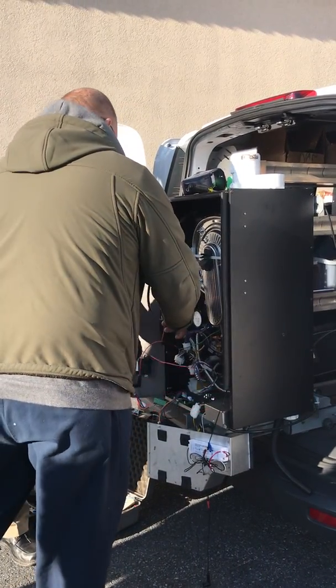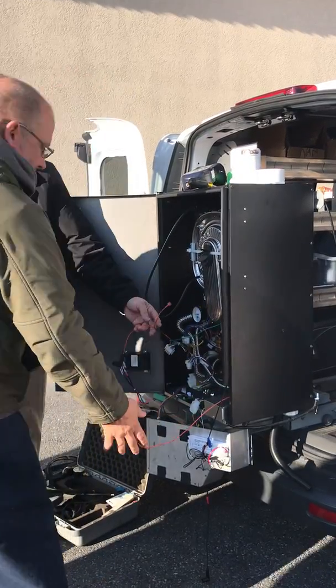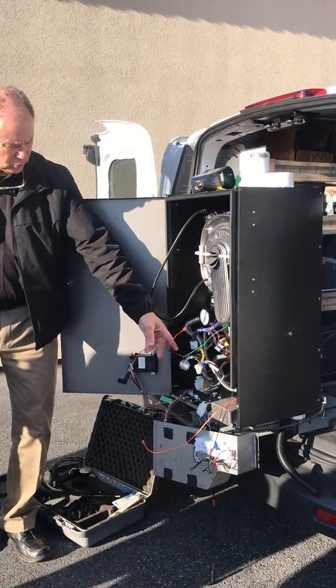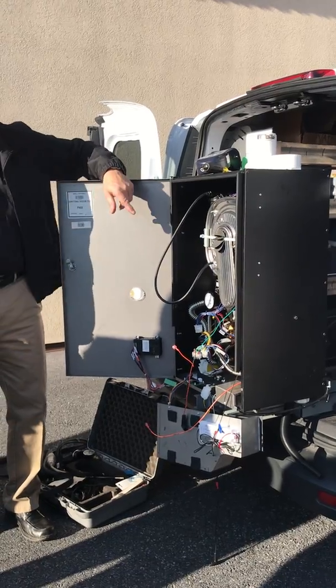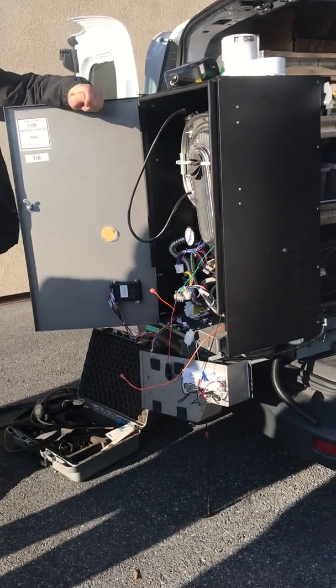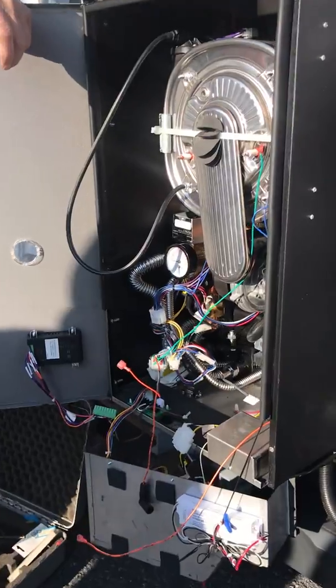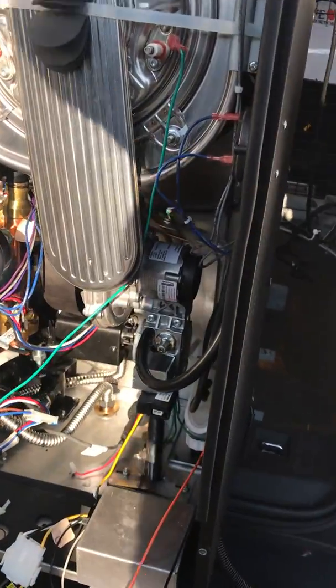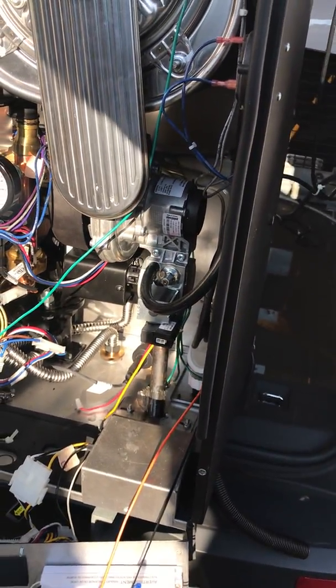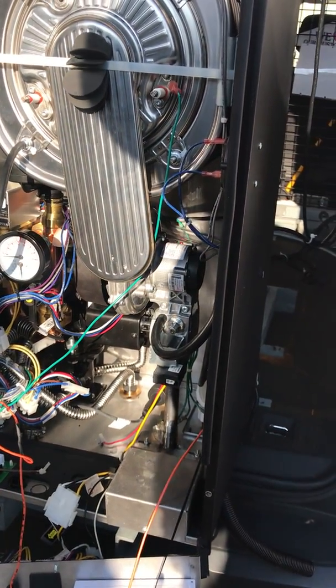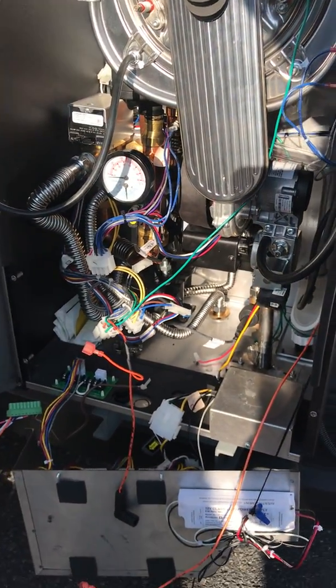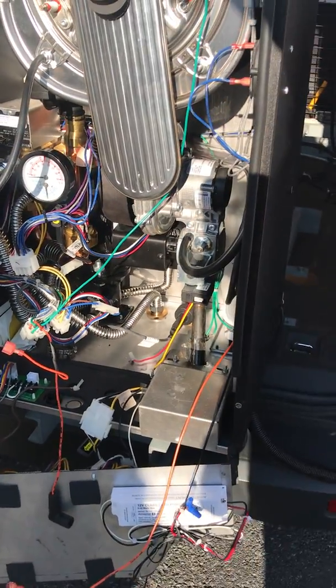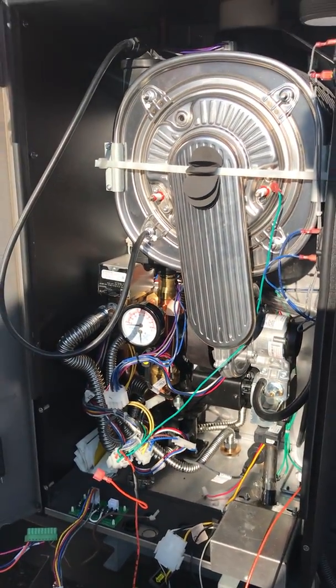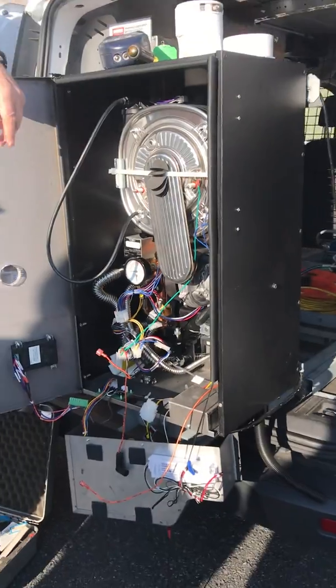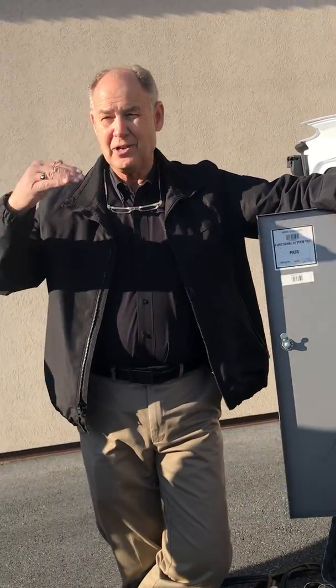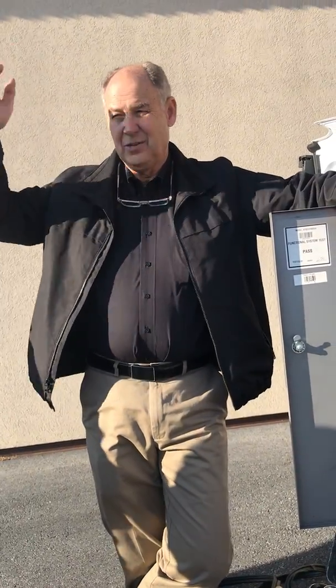And you're putting one of these in, do what he just did. Take this wire that goes down to the condensate and take it off. Or if you have one that's already installed and you're getting flame failures, you should not get flame failures. And this will give you the error codes on what you have. But if you do get flame failures, you can actually look at your flame signal where it lights. And this will tell you whether you're in low fire, you're 20%, you're 60%, so you can see what it is.